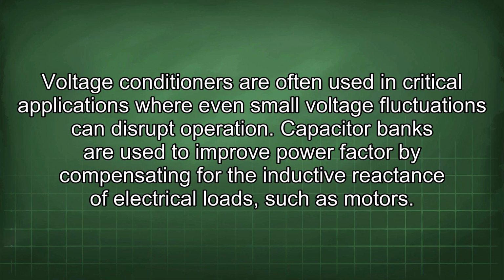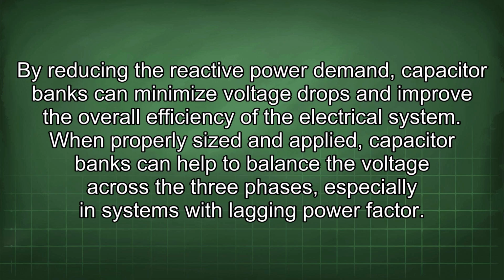Capacitor banks are used to improve power factor by compensating for the inductive reactance of electrical loads such as motors. By reducing the reactive power demand, capacitor banks can minimize voltage drops and improve the overall efficiency of the electrical system. When properly sized and applied, capacitor banks can help to balance the voltage across the three phases, especially in systems with lagging power factor.